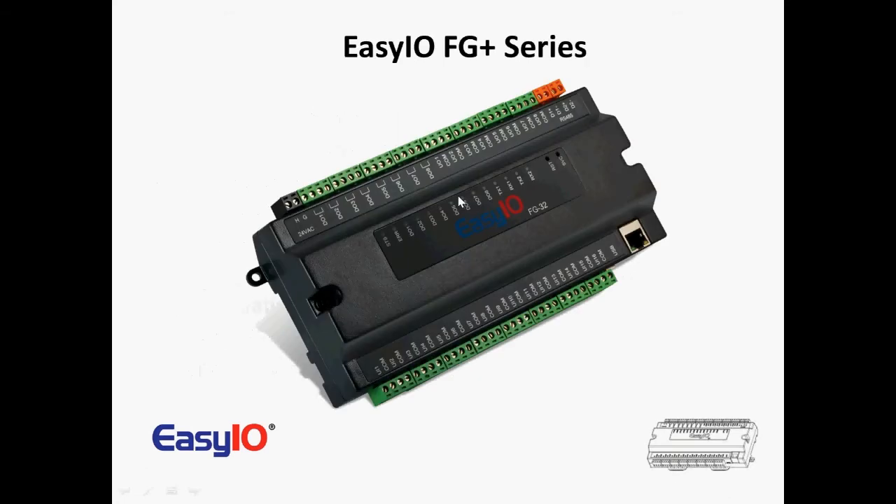So moving ahead, there's the FG32. As you can see, we've got 16 inputs, 16 outputs, and 16 universals — they can be voltage, current, or resistance. 16-bit resolution, so we can read anybody's sensors up to 500,000 ohms. On the outputs, we've got digital outputs with volt-free contacts rated at 24 volts at 24 VA. And we've got eight analog outputs. We also have two serial ports. The outside one, D2, is for Modbus and EnOcean. And D1 is for the BACnet MSTP — we have client and server. And on the Modbus, we have master and slave.